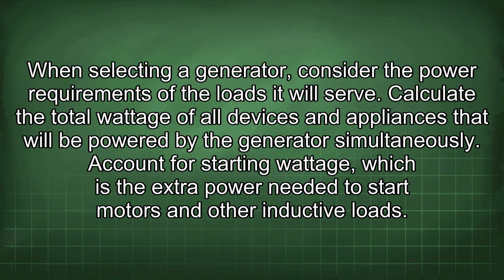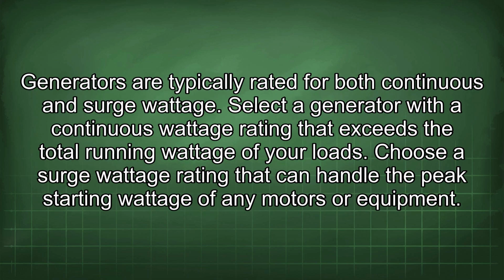When selecting a generator, consider the power requirements of the loads it will serve. Calculate the total wattage of all devices and appliances that will be powered by the generator simultaneously. Account for starting wattage, which is the extra power needed to start motors and other inductive loads. Generators are typically rated for both continuous and surge wattage. Select a generator with a continuous wattage rating that exceeds the total running wattage of your loads. Choose a surge wattage rating that can handle the peak starting wattage of any motors or equipment.